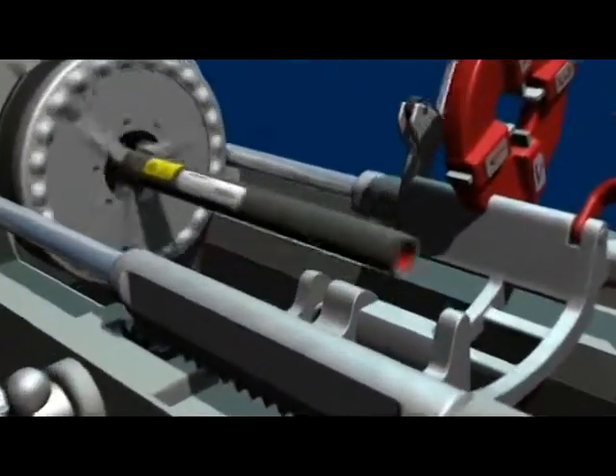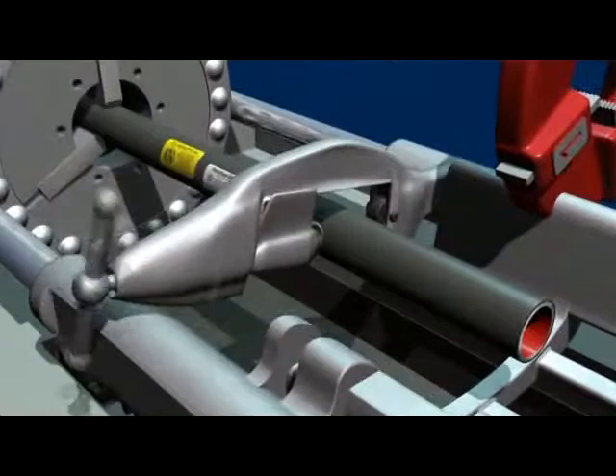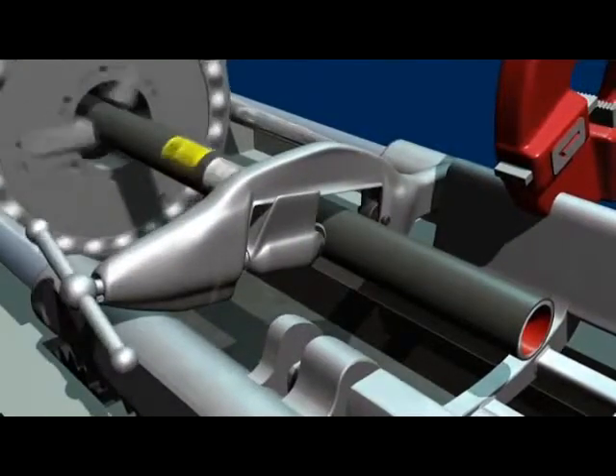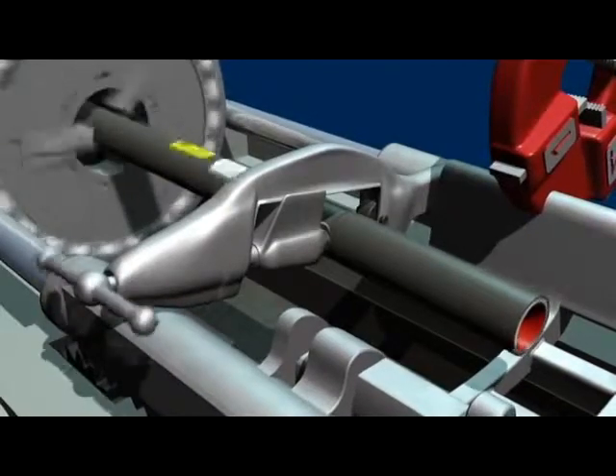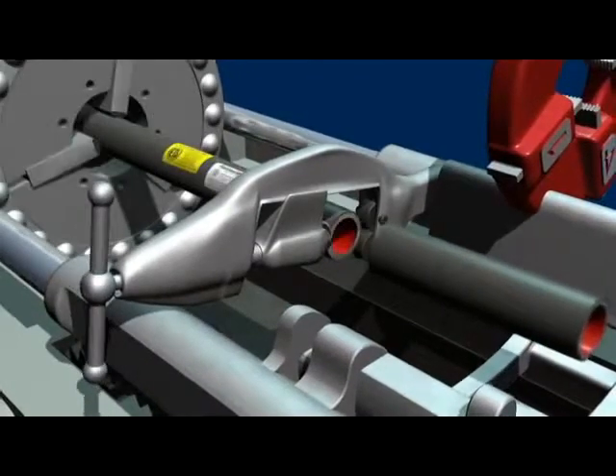PlastiBond recommends using a roller cutter to cut coated conduit. In addition to producing a square cut end, the roller cutter will remove approximately one quarter inch of the PVC coating, aiding in conduit threading.